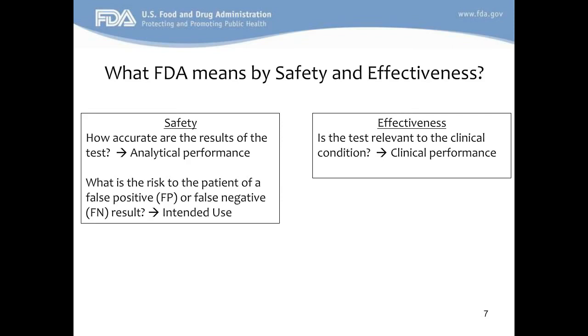So if you're measuring a particular analyte in, say, serum or plasma, the analytical performance needs to be tested, and studies need to be performed to look at, for instance, the accuracy of the device, the linearity, the precision, and the reproducibility of the device. We evaluate the analytical performance to determine whether the device actually is able to measure reproducibly and well the analyte that it's intended to measure.